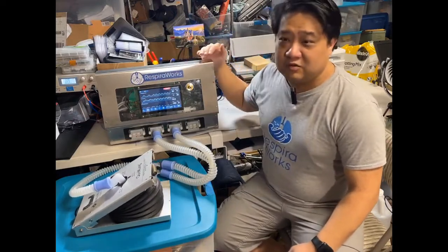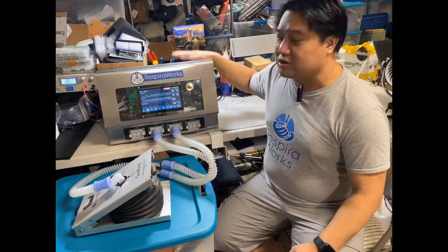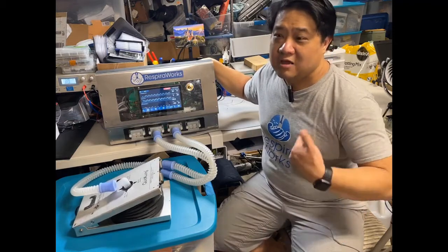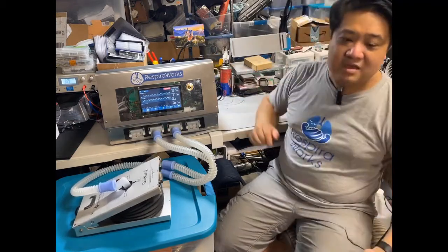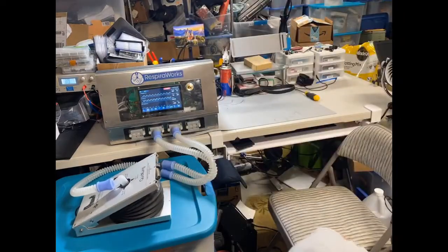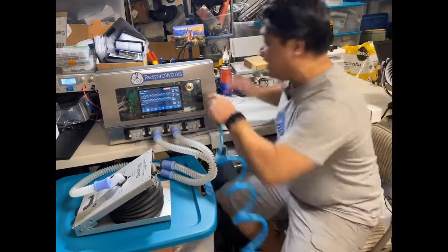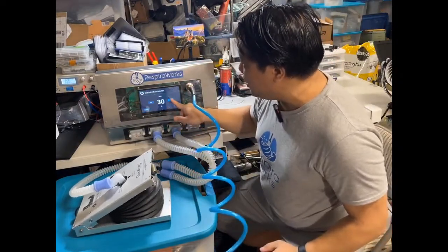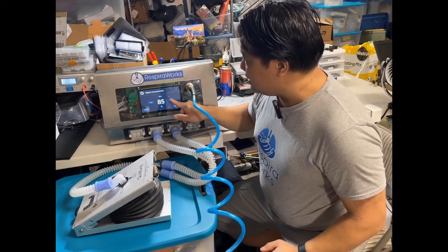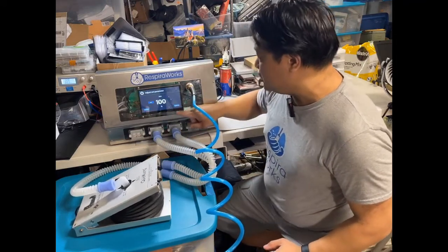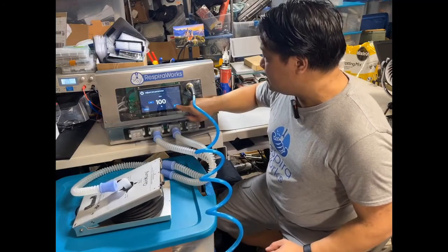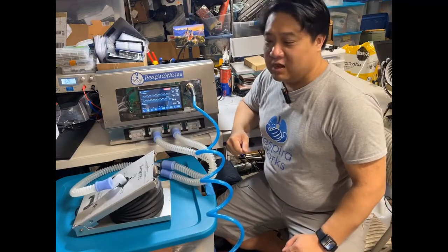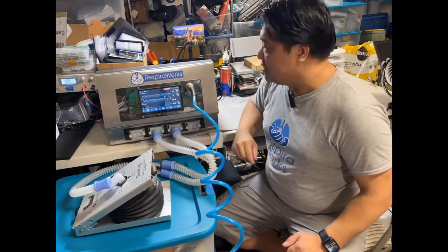Now, if the patient requires supplemental oxygen, the ventilator is also capable of controlling off a standard pressurized oxygen hospital oxygen supply at 50 psi. So we actually have a compressed air tank here to act as a stand-in, and I'll go ahead and connect that now. And for demonstration, we're going to set the FiO2 all the way to 100% to demonstrate pure oxygen control. So you hear the blower shut down there, and the vent now running, delivering to the patient off of the supplied oxygen.